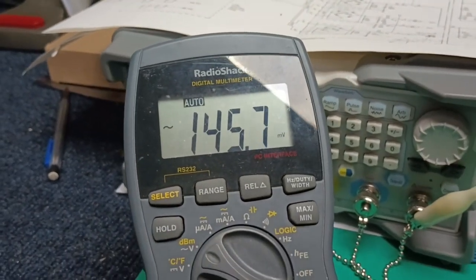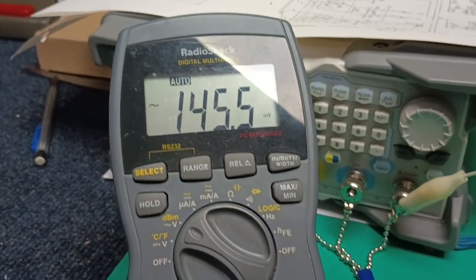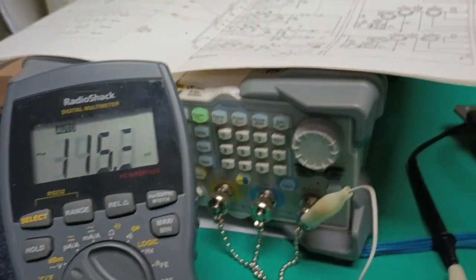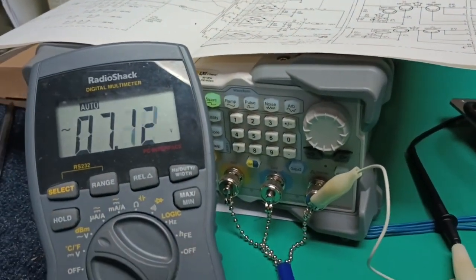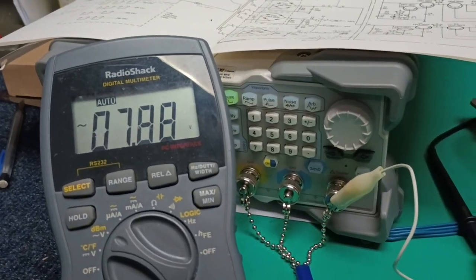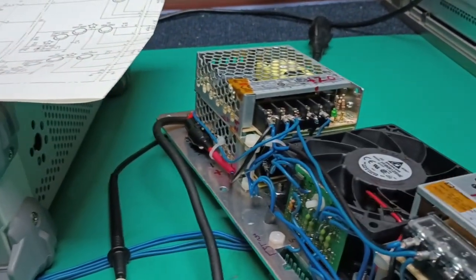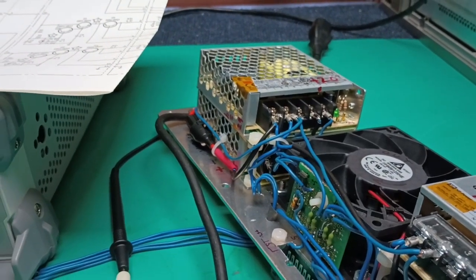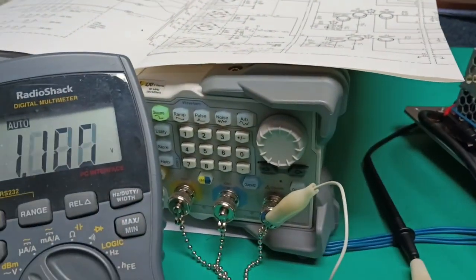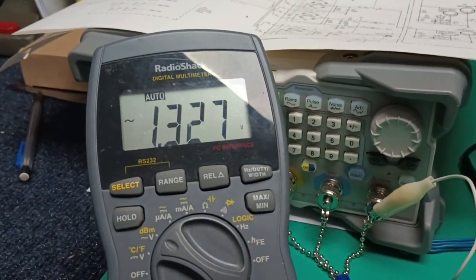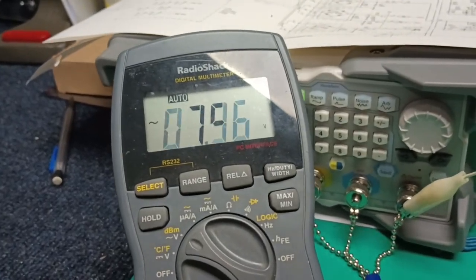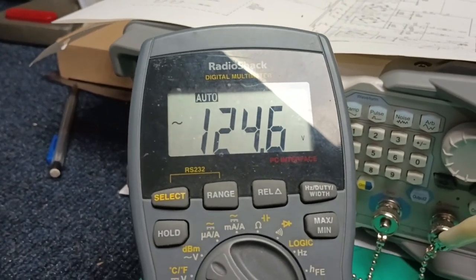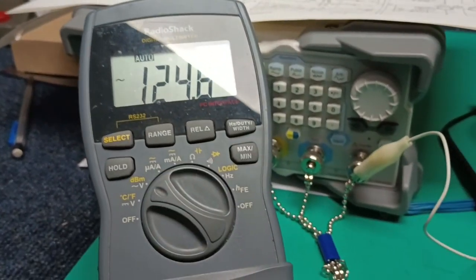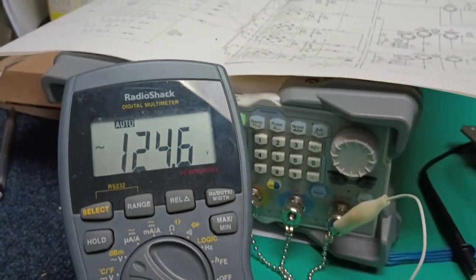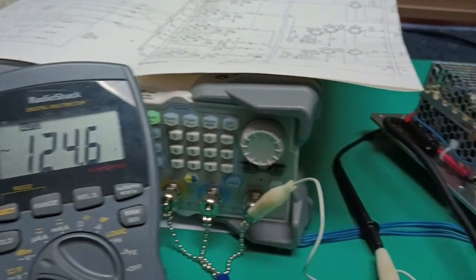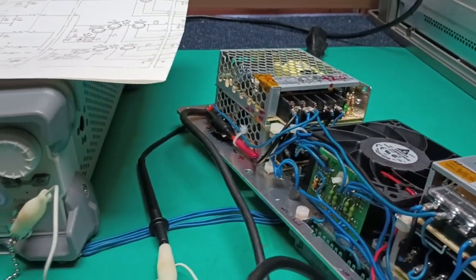Why? Why is that suddenly a very low value? Well, because this generator back here has an AC power cord with the neutral line reference to the chassis, and the neutral in these power supplies are also referenced to the same neutral. So there's essentially no voltage drop across the two. We touch the L1 terminal, and there it is, 124 volts AC. So what that means is that there's something odd inside these power supplies, something causing AC leakage.